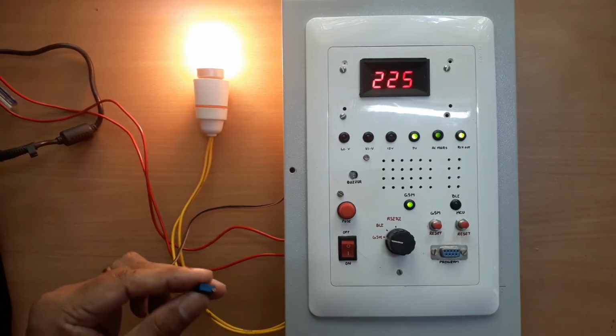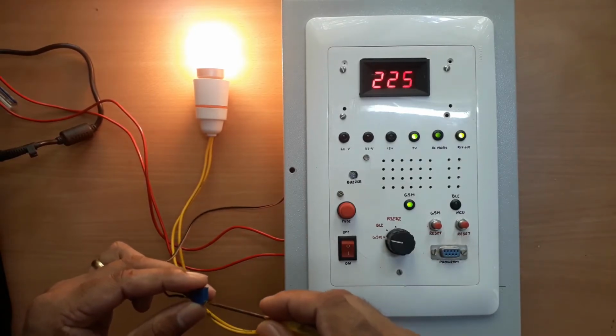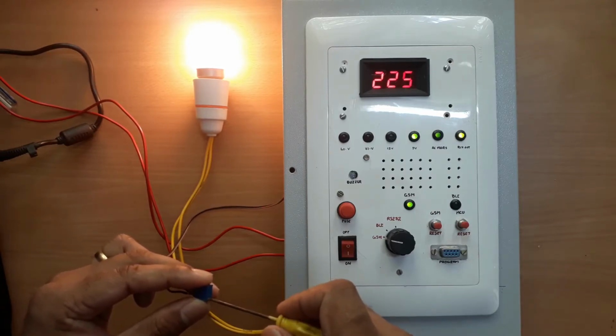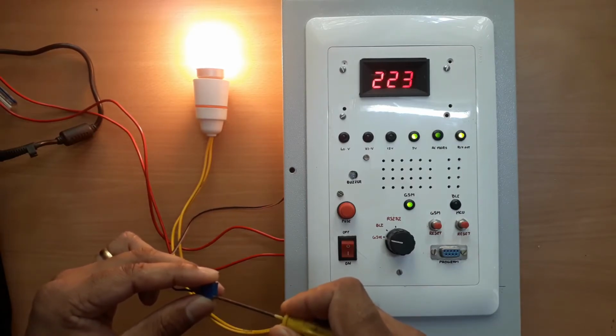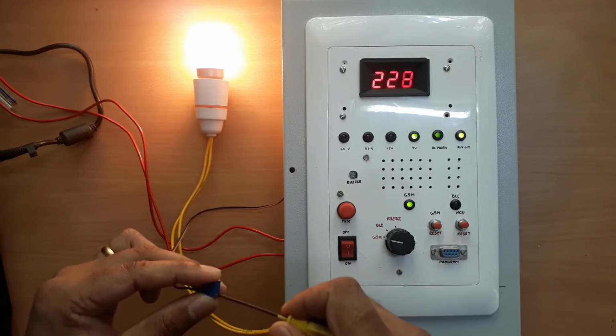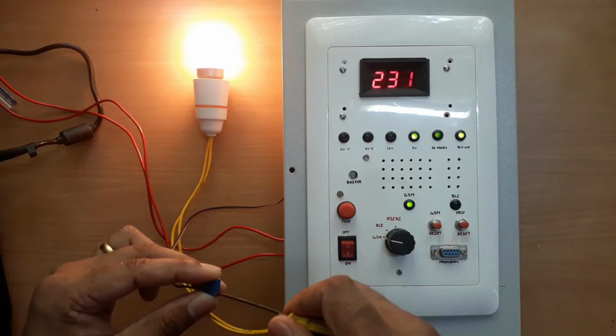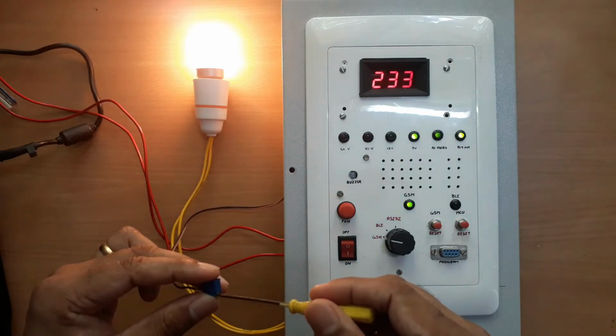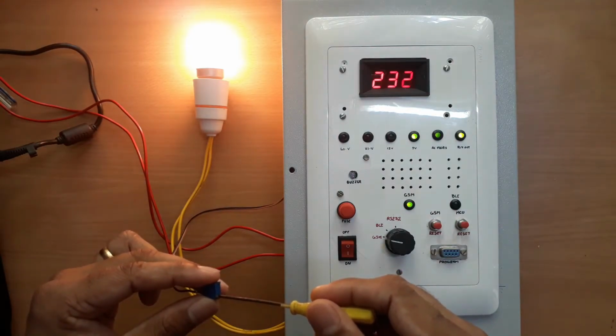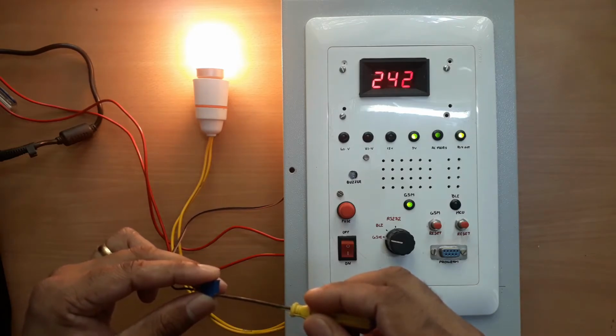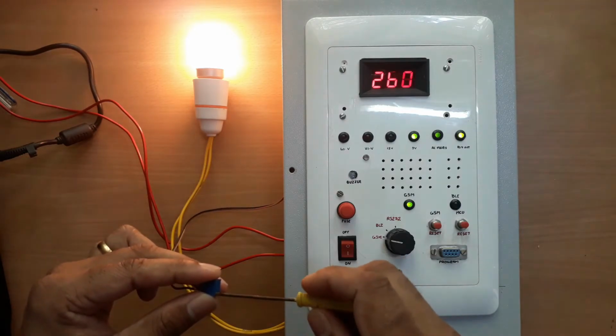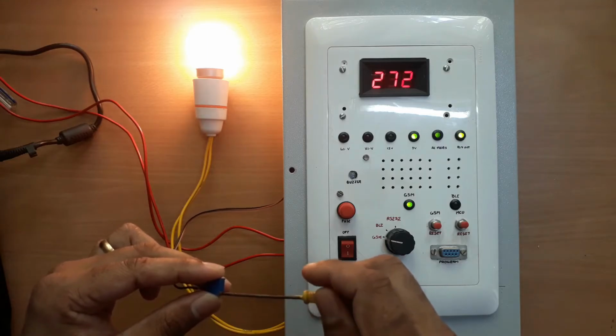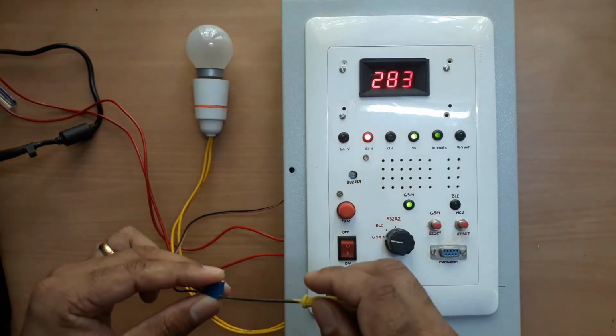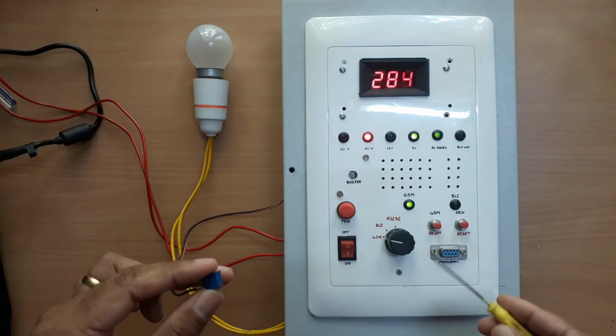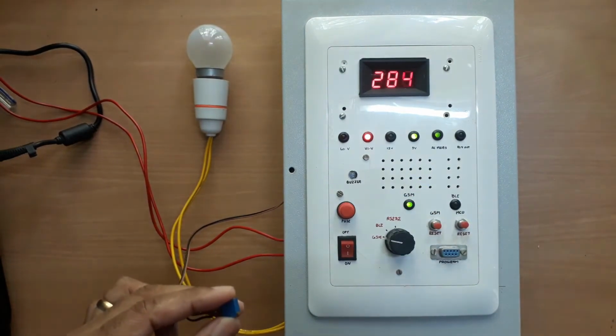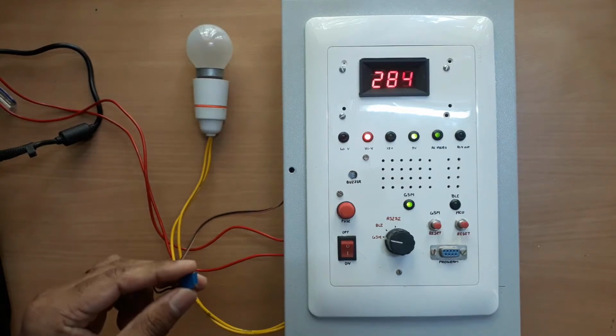We configured the upper cutoff voltage at 280 volts and the lower cutoff voltage at 170 volts. We are increasing the output voltage by turning the potentiometer, from 226 volts to 233, then further to 242 volts, and it keeps rising toward 280 volts. The relay turns off when the input voltage goes higher than 280 volts - that is our upper cutoff value, and the high voltage LED will also glow there.